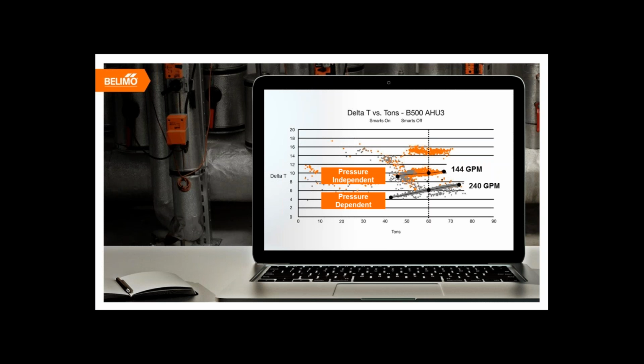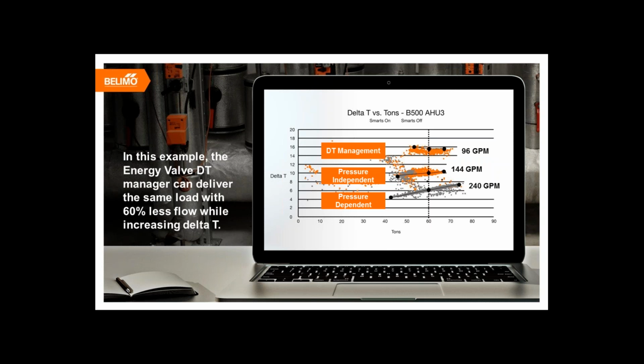Then finally, in the same air handling unit in the same building, we turned on the delta T management feature of the Energy Valve. We set a delta T for a 15-degree set point, and we were able to reduce the flow to maintain the same 60-ton load all the way down to 96 GPM. This is a savings of 60% less flow while maintaining the load and increasing the delta T.